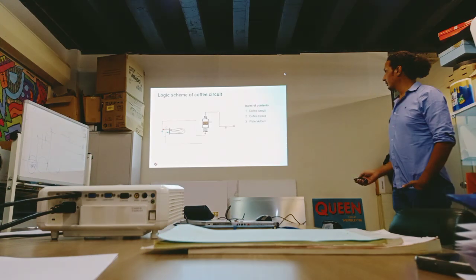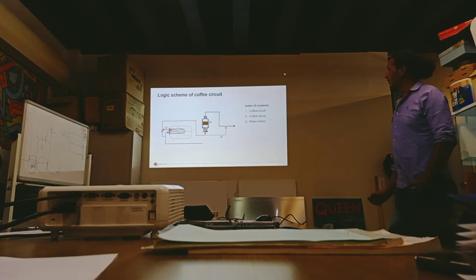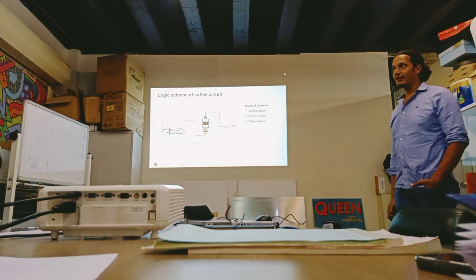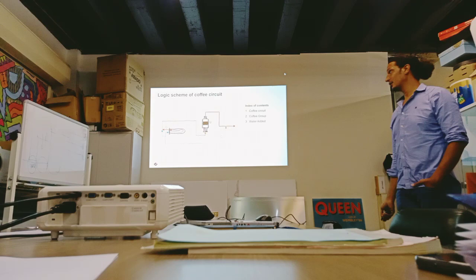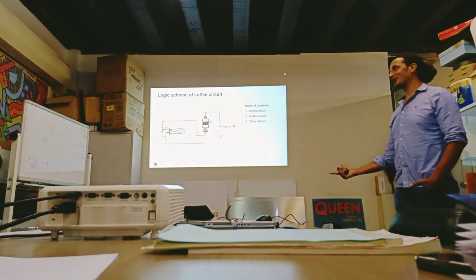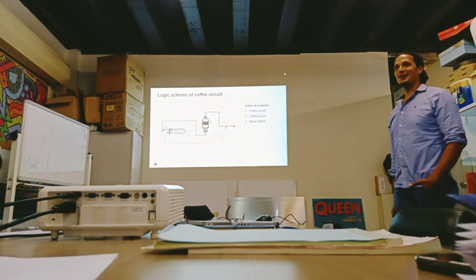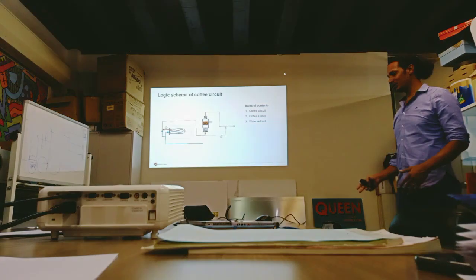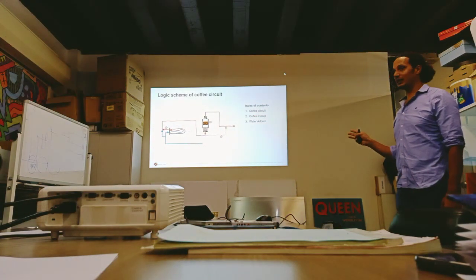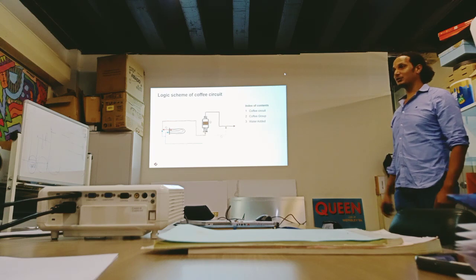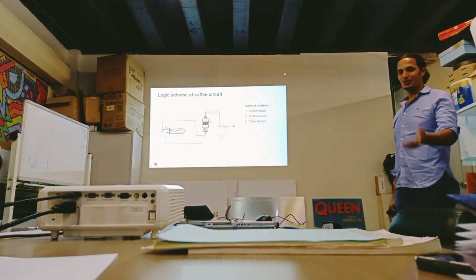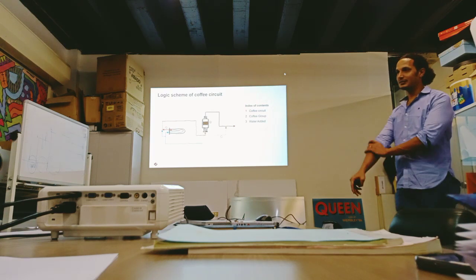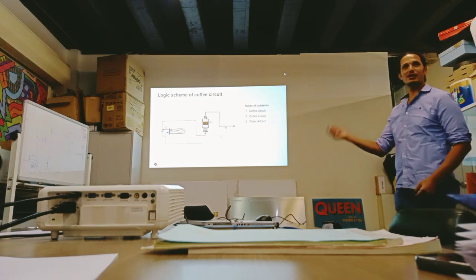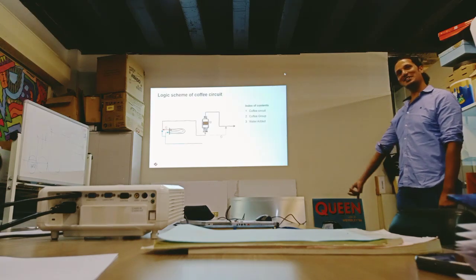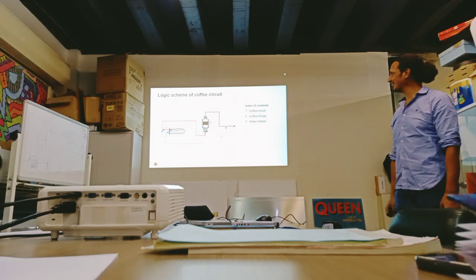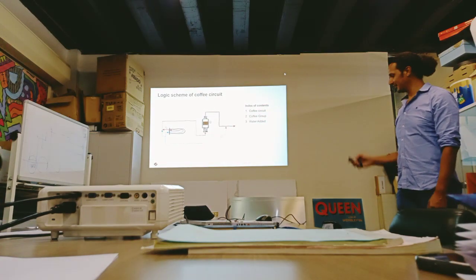Next. So the machine should be hot first? To empty it? No, it does not need to be hot to empty it. It's a situation where I go to a machine, I need to work on it and it's hot, so this is the way to empty the boiler. If I go to a machine that is switched off, I just open and drain directly from the boiler, mechanically. Don't switch it on to heat up and then drain 70%, or wait for it to cool down. Just open and empty.